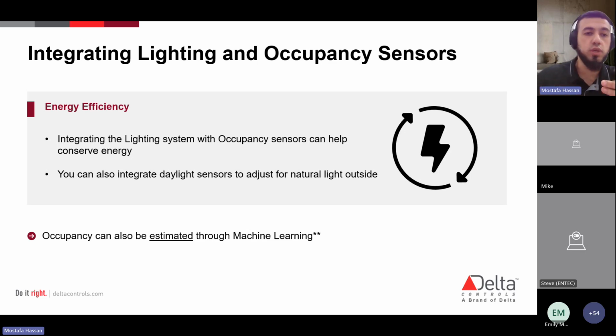Now, here's the best part. If you incorporate daylight sensors into the space to adjust for natural light, then you get even more optimization. You don't have to turn on the light up to 100% if there's daylight outside and you have the windows open. So with daylight sensors, you can use daylight harvesting, depending on the amount of natural light available. If there's sufficient daylight, the light is dimmed to 50%, and the system continuously monitors occupancy to adjust the light in the space.